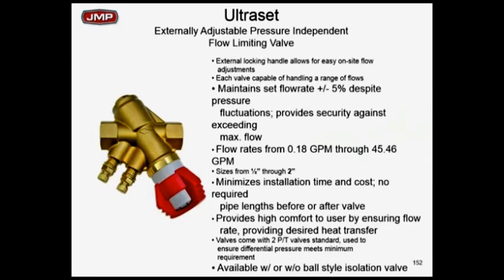So now if you know the position of the valve, you know the flow. The two-way valve sees a constant differential pressure. That's critical. Here's a product that we sell where you can actually read the flow in GPM and set it. That's a pretty neat idea. You can actually dial in the flow you want in GPM, with a little red dial there.